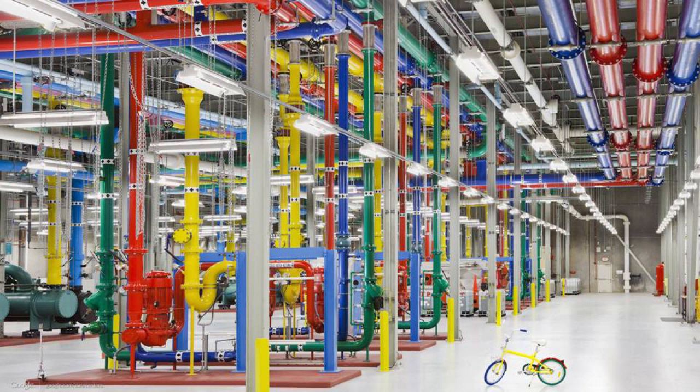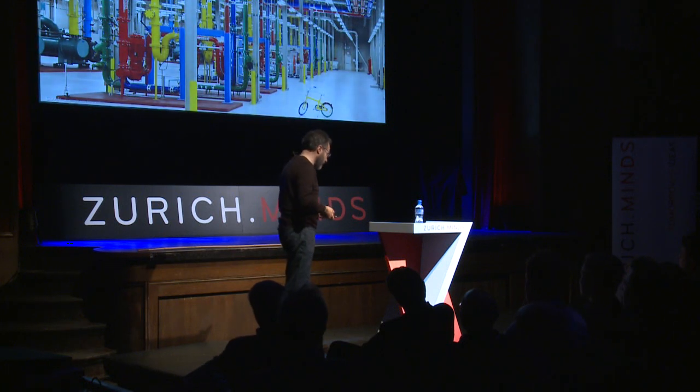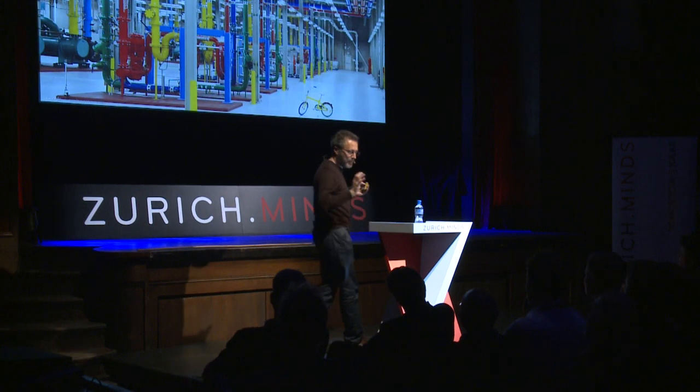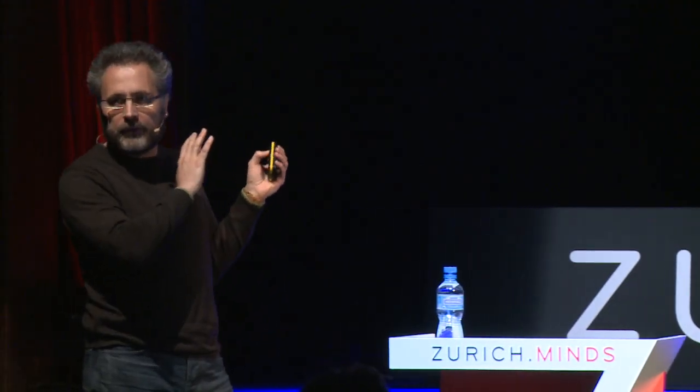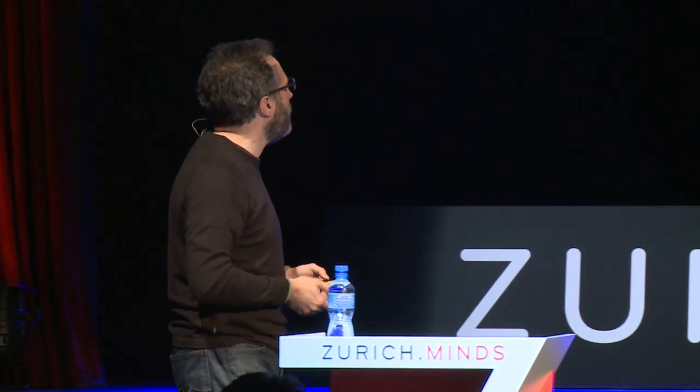So in this particular data center, that heat goes into a cooling tower, and that cooling tower just evaporates water. And as you know, it takes a lot of energy to boil water. It takes even more energy to evaporate water. So when you evaporate water, you can remove a lot of heat very, very easily. Basically, the natural environment does it for you. And in this particular case, we actually built a water treatment plant so that we can use slightly treated, recycled water for that whole process.